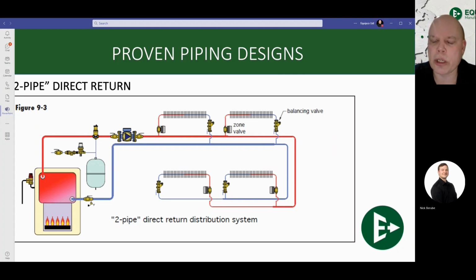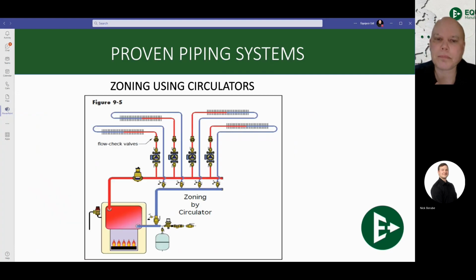There are simpler ways to do it, and this one can get a little bit confusing on the installation side of things. Plus you need to increase and decrease. It's in your best interest, I should say, to increase your pipe sizing as your system returns and decrease it as your system is supplying out into those rads. So a little more math is required, or we can do it easier nowadays, but this style does work provided that it's installed and designed correctly.